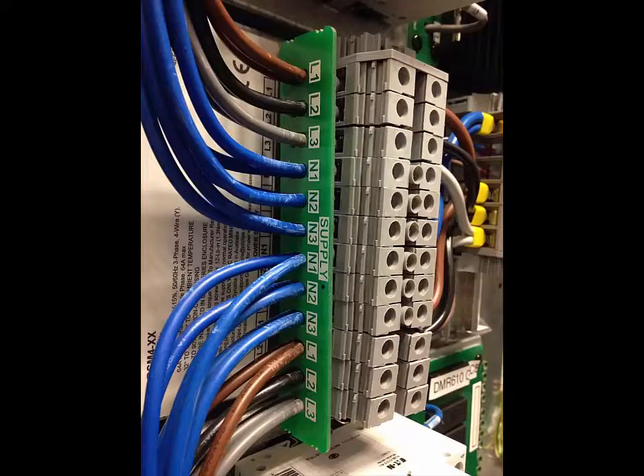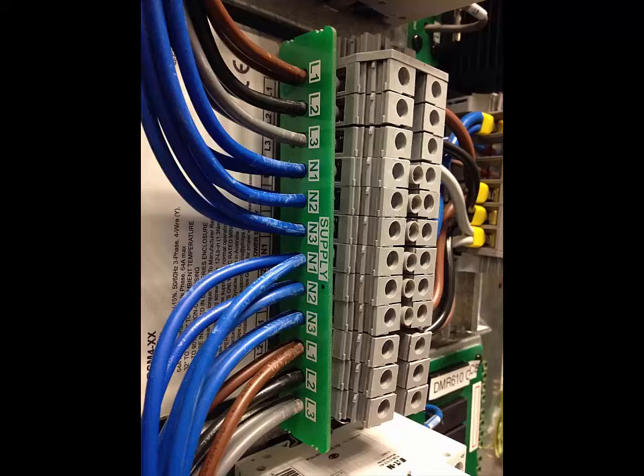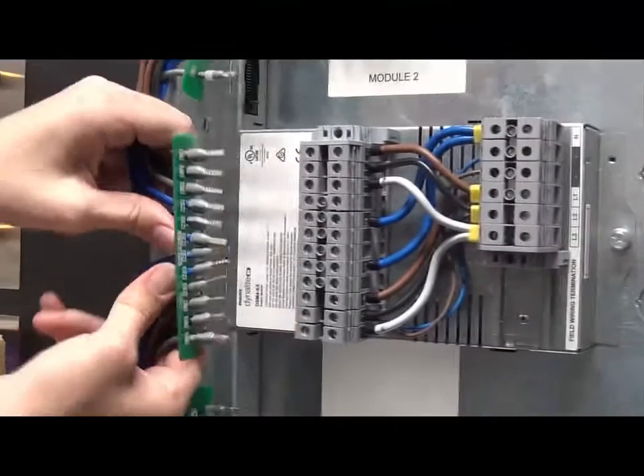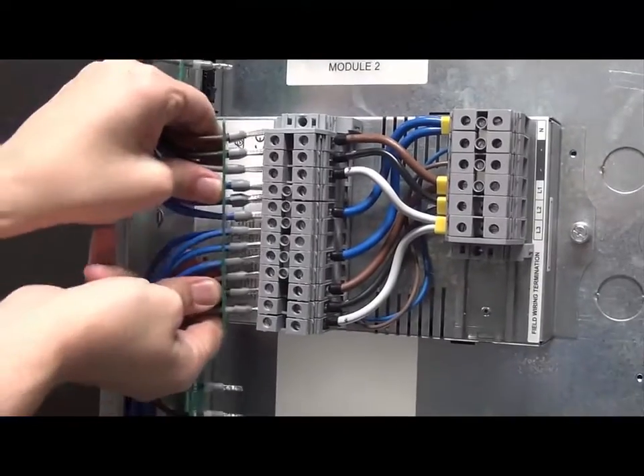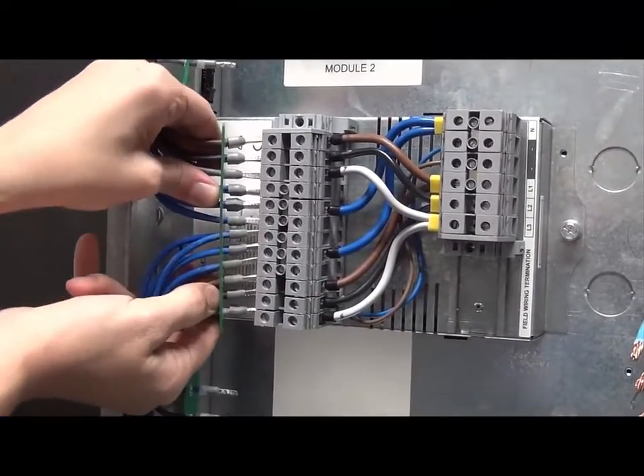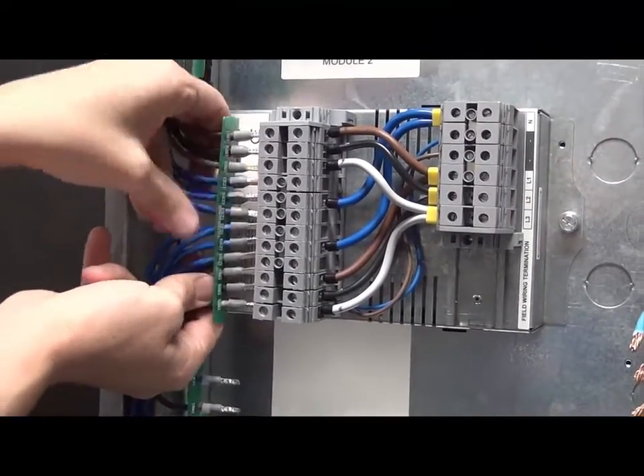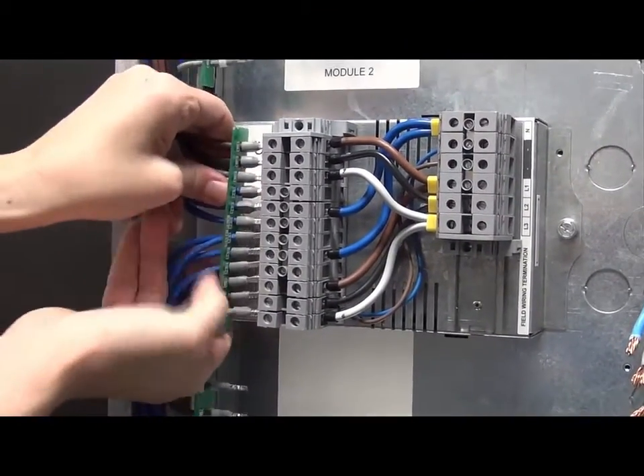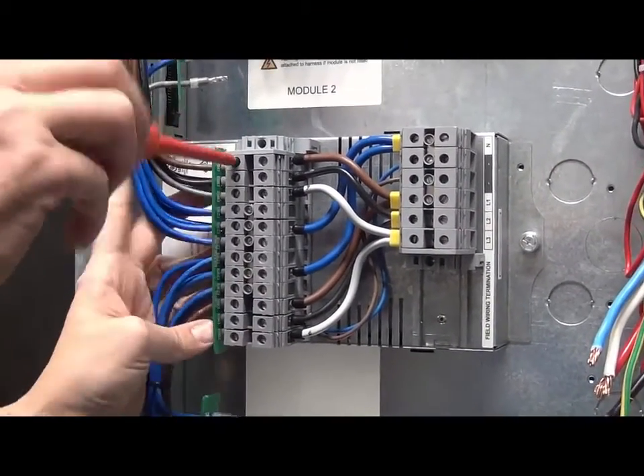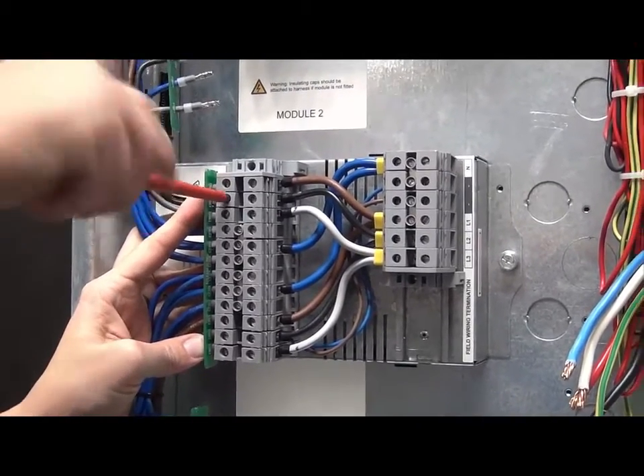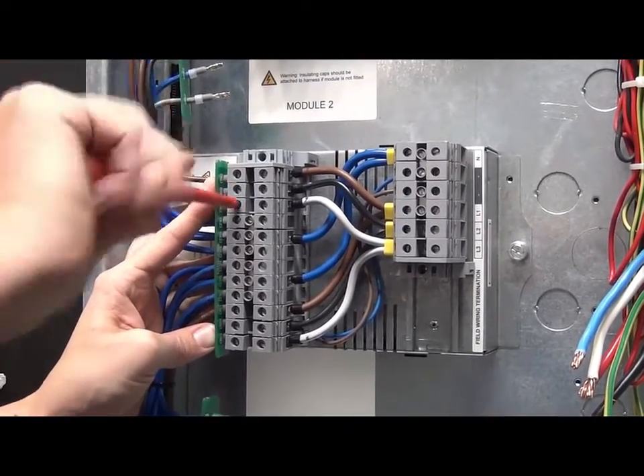For correct operation of the unit, ensure that the supply on Phase L1 is always present. Terminate the supply group of the wiring loom into the left-hand side of the terminals. Check all terminal screws are properly tightened.